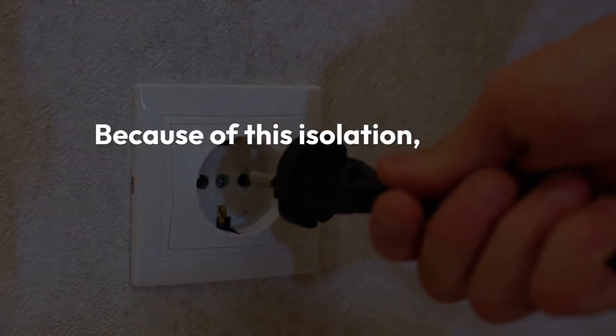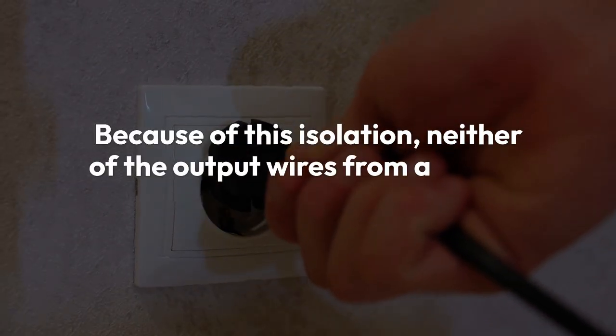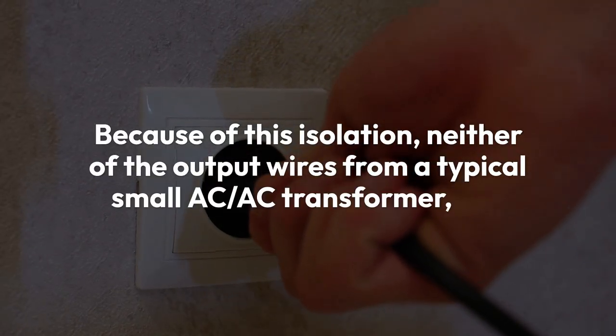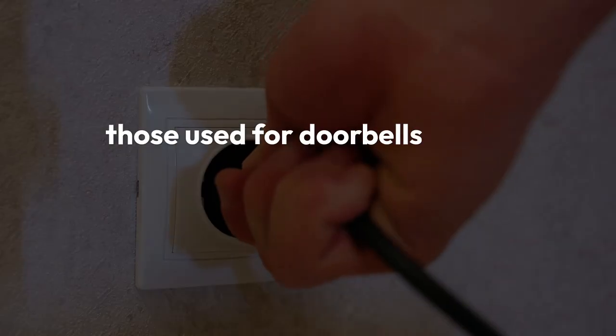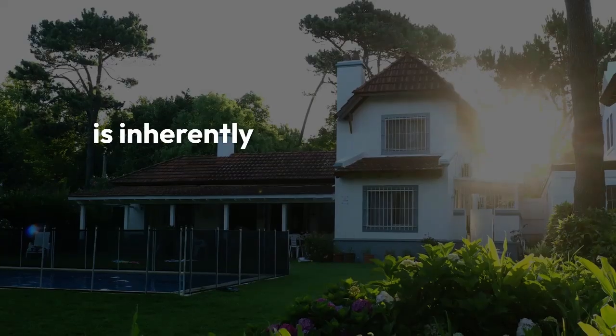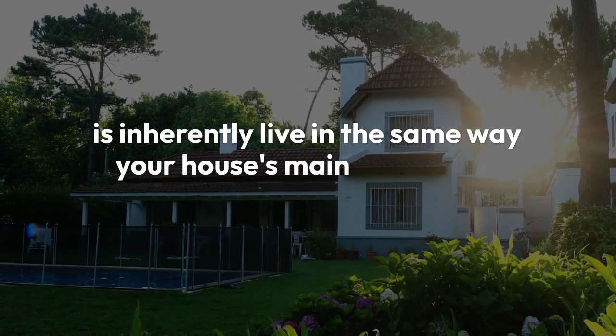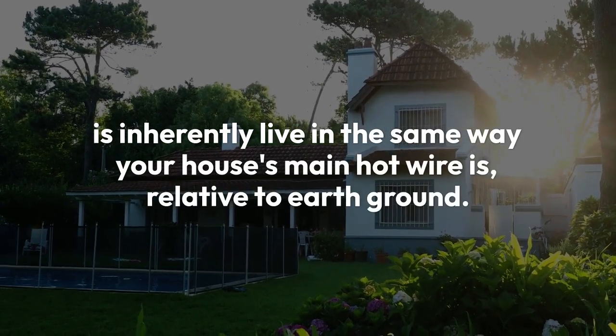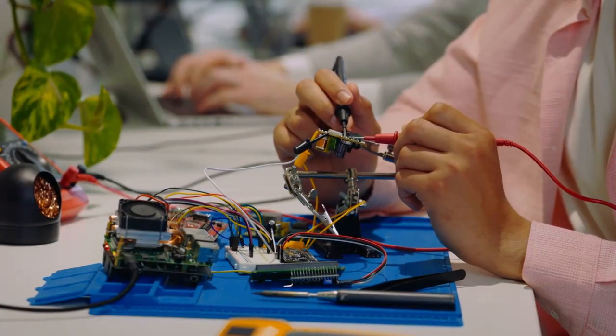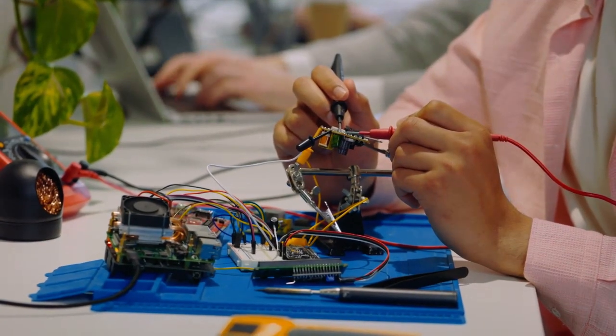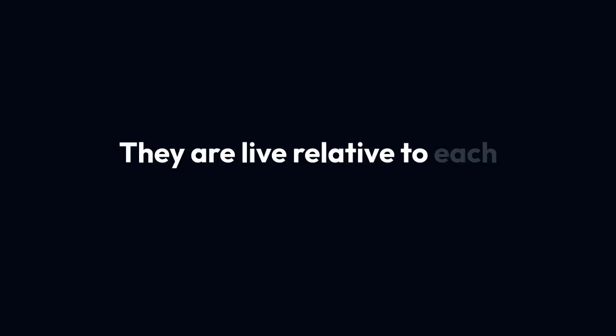Because of this isolation, neither of the output wires from a typical small AC/AC transformer, like those used for doorbells or low-voltage lighting, is inherently live in the same way your house's main hot wire is, relative to earth ground. Instead, the voltage exists between the two output wires. They are live relative to each other.